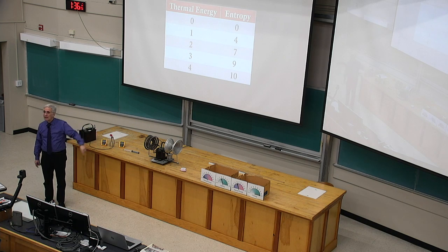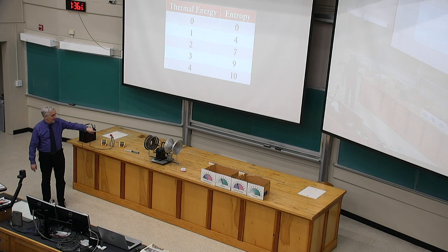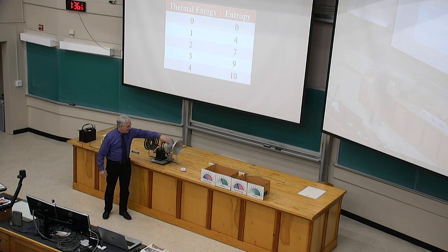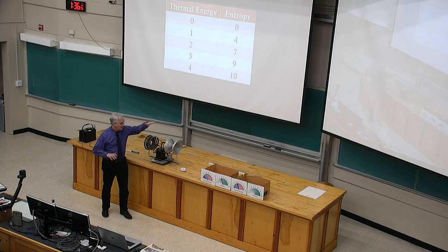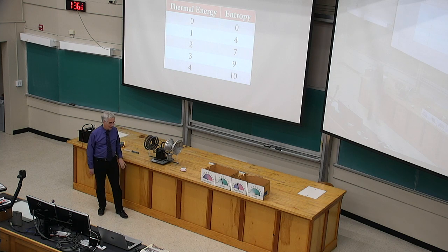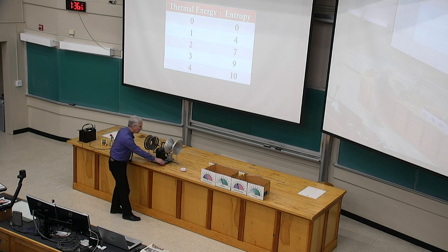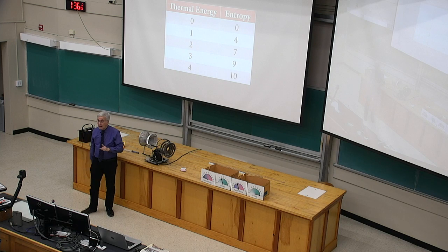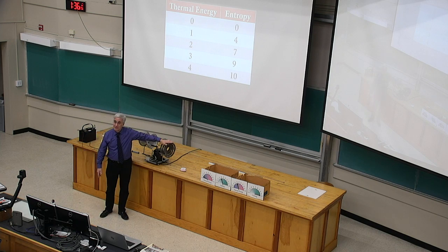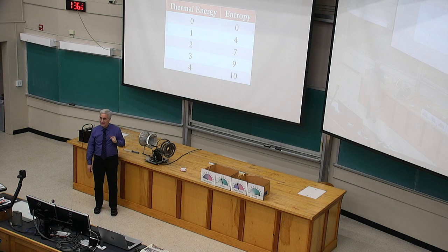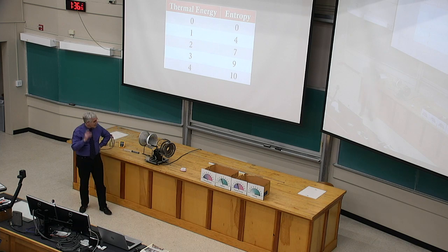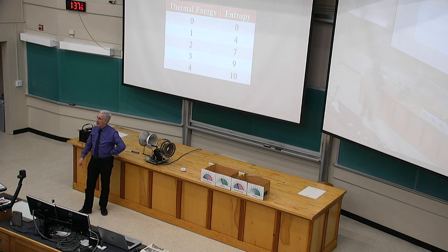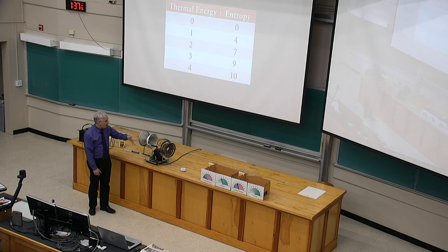This same structure can be used for heating a house. As I've described it so far, it's air conditioning a house. And so you put the evaporator indoors, the condenser outdoors, heat is soaked up from indoors and dumped outdoors, and that's that. But if you turn it around, okay, I'll be dramatic here, and I'll literally turn it around. Now, the indoor unit is the condenser, and the outdoor unit is the evaporator. And why would you do this? Well, in the winter, when you want to heat your house, you can operate this way.